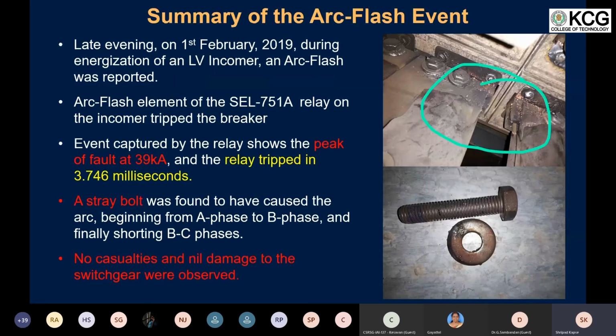For this particular installation, on 1st of February 2019, we saw an arc flash event occur. In this arc flash event, the actual peak fault current on the 415 volt side went up to 39 kiloamperes. And the relay operation time in this case was measured to be about 3.76 milliseconds. Due to this fast operating time of the relay, based on the arc flash protection, we were able to mitigate the hazard associated with the arc flash significantly.